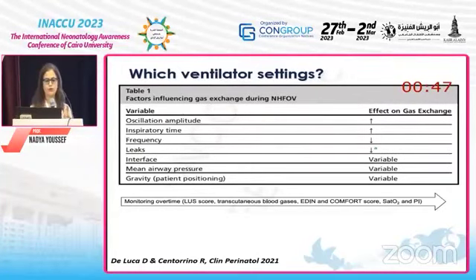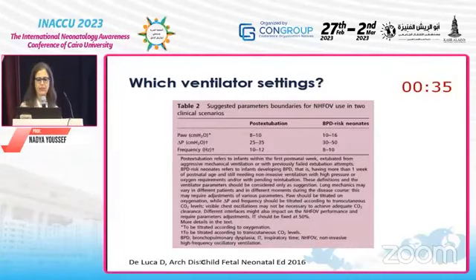We do know that by changing the amplitude, the inspiratory time, frequency, and pressure we will be able to have an effect on gas exchange. However, we're also faced with the problem of leaks. So what we would suggest, or this paper suggests, is that when it is in post-extubation, we start around 10 centimeters of mean airway pressure, with an amplitude around 25 to 35 and a frequency around 10 to 12. However, if we're faced with the BPD population that are at high risk of re-intubation, we have much higher settings. This is non-invasive, so we shouldn't be afraid to go up. So the pressures will go up to 16 with an amplitude of 50 and a frequency as low as 8.